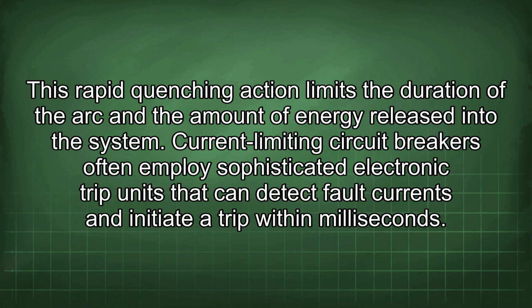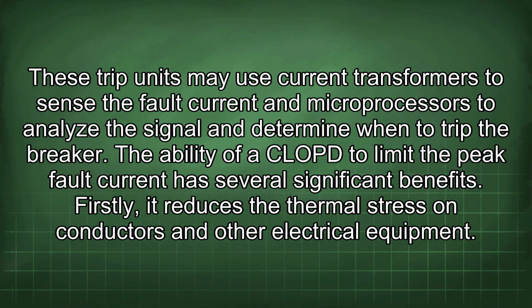Current-limiting circuit breakers often employ sophisticated electronic trip units that can detect fault currents and initiate the trip within milliseconds. These trip units may use current transformers to sense the fault current and microprocessors to analyze the signal and determine when to trip the breaker. The ability of a CLOPD to limit the peak fault current has several significant benefits.